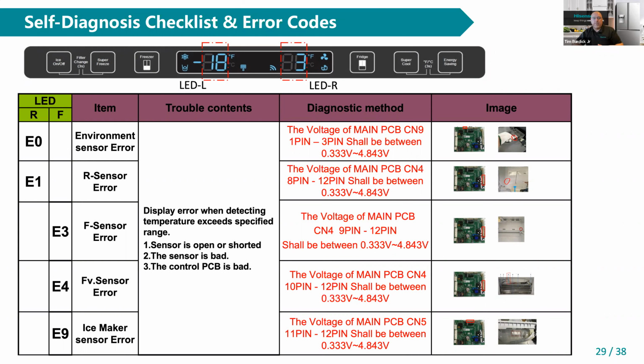For example, take the E3 sensor code - that's my fresh food sensor. If I have an issue there, it's not cooling properly, I need to check that code. I go back to the main control board, and on connection number 4 between pins number 9 and 12, I should be reading somewhere between 0.33 volts and 4.84 volts DC. If I'm out of those specs, then depending on the temperature, I need to replace either the sensor or the control board, whichever isn't giving the proper information.